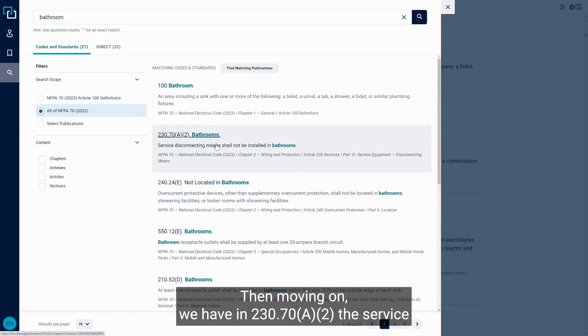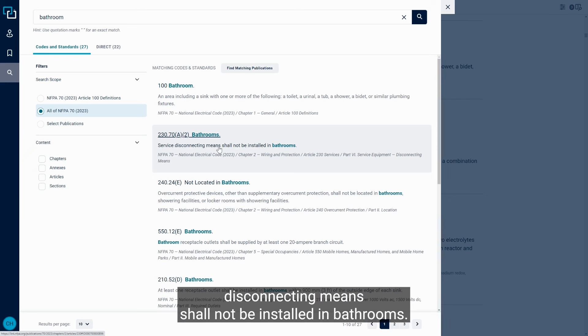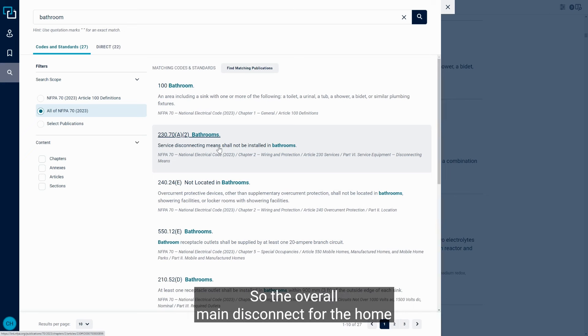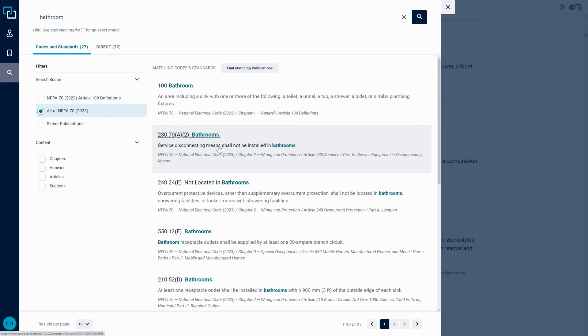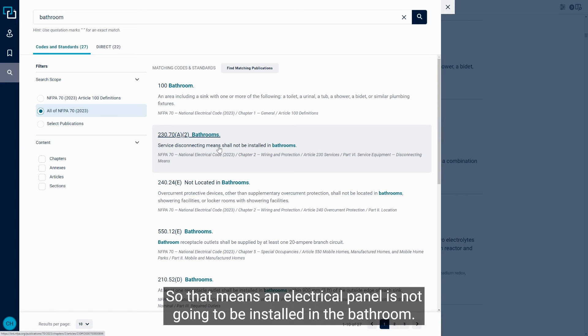Then moving on, we have in 230.70.A.2, the service disconnecting means shall not be installed in the bathroom. So the overall main disconnect for the home cannot be installed in the bathroom. So that means an electrical panel is not going to be installed in the bathroom.